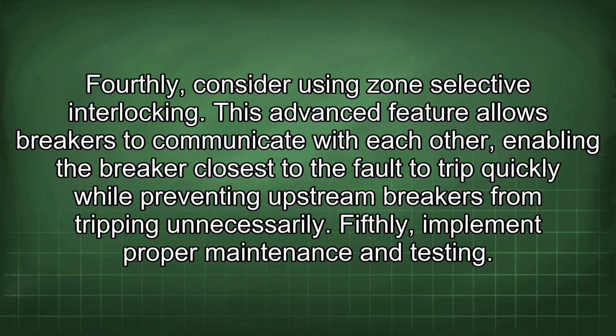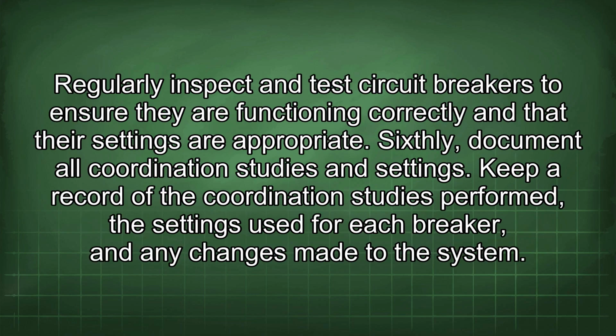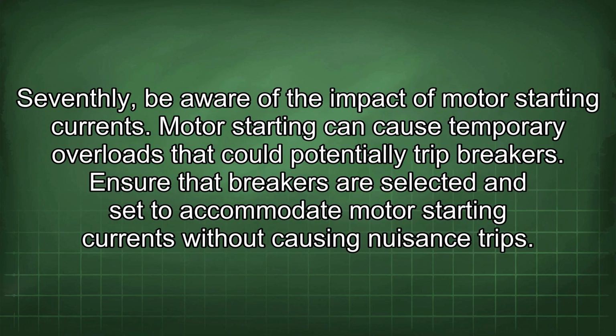Fourthly, consider using zone-selective interlocking. This advanced feature allows breakers to communicate with each other, enabling the breaker closest to the fault to trip quickly while preventing upstream breakers from tripping unnecessarily. Fifthly, implement proper maintenance and testing. Regularly inspect and test circuit breakers to ensure they are functioning correctly and that the settings are appropriate. Sixthly, document all coordination studies and settings. Keep a record of the coordination studies performed, the settings used for each breaker, and any changes made to the system.